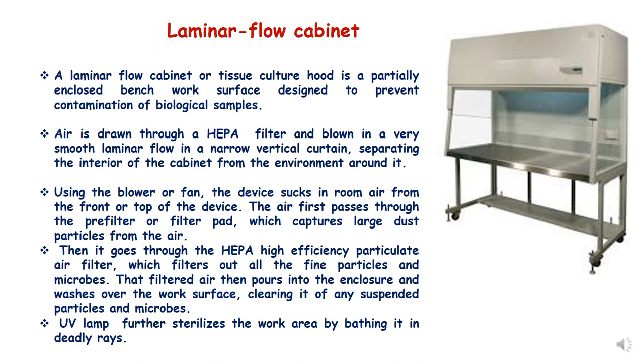The next requirement of a tissue culture lab is the laminar flow cabinet. A laminar flow cabinet is a tissue culture hood — a partially enclosed bench workstation designed to prevent contamination of biological samples. Inside the cabinet, air is drawn through a HEPA filter, which stands for High Efficiency Particulate Air filter, and blown in a smooth laminar flow in a narrow vertical curtain separating the interior of the cabinet from the surrounding environment.